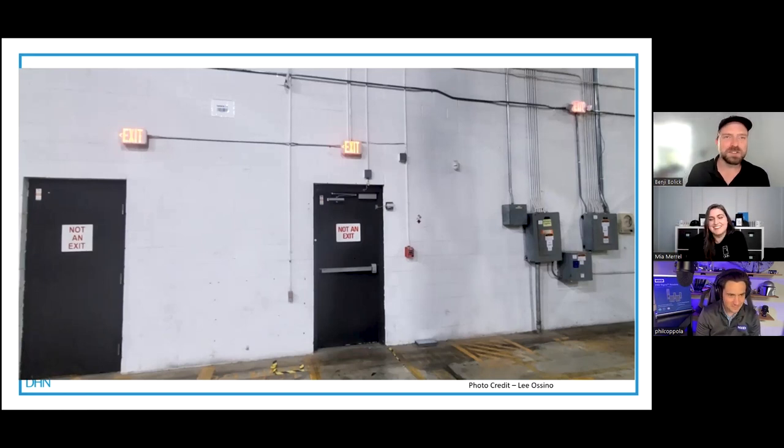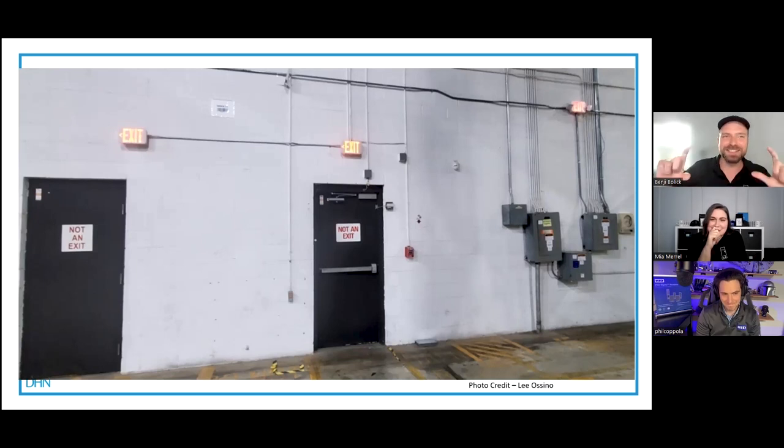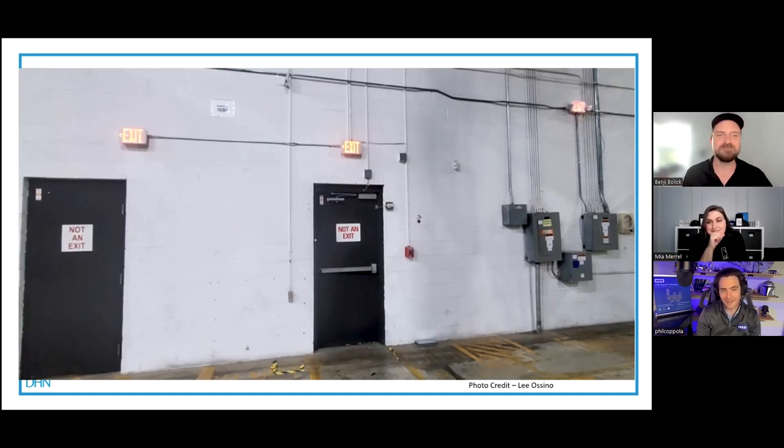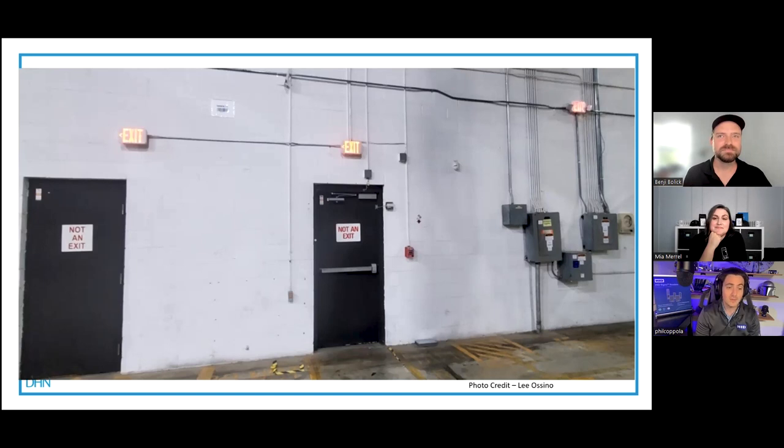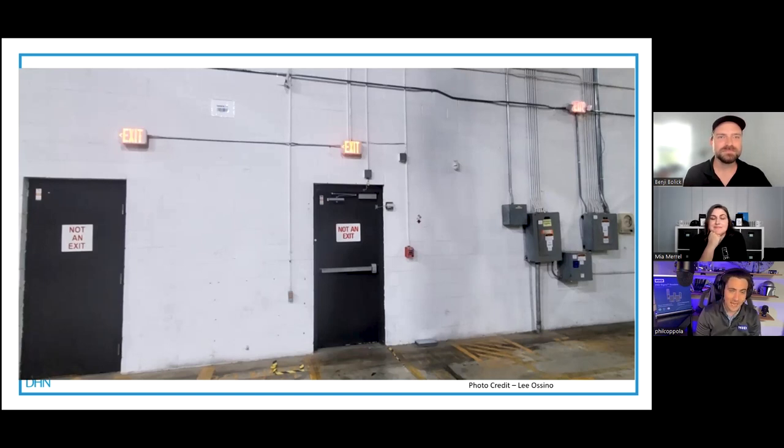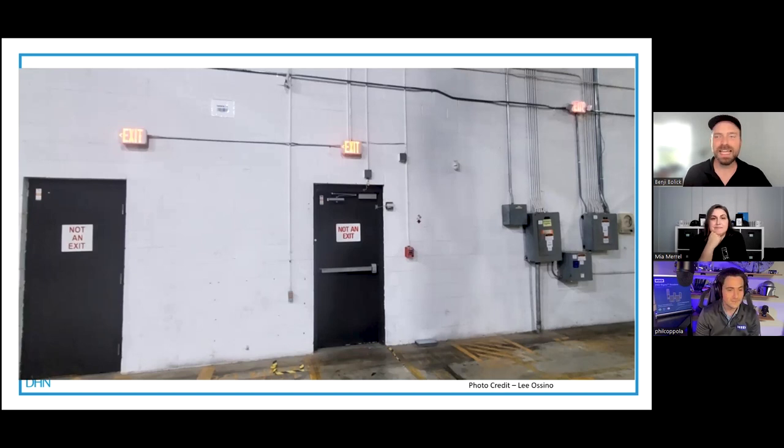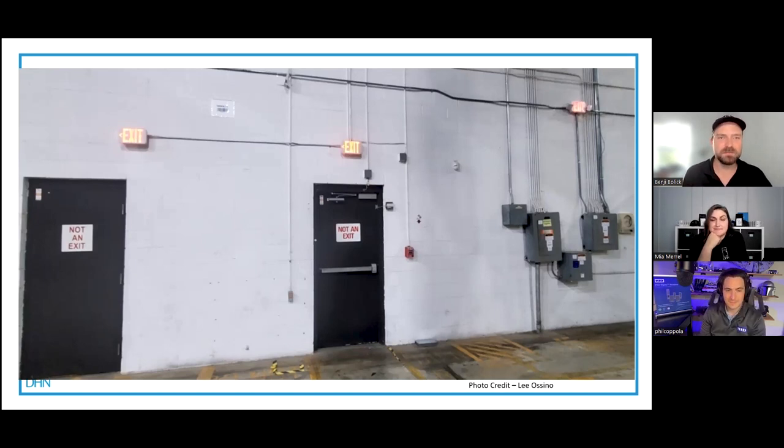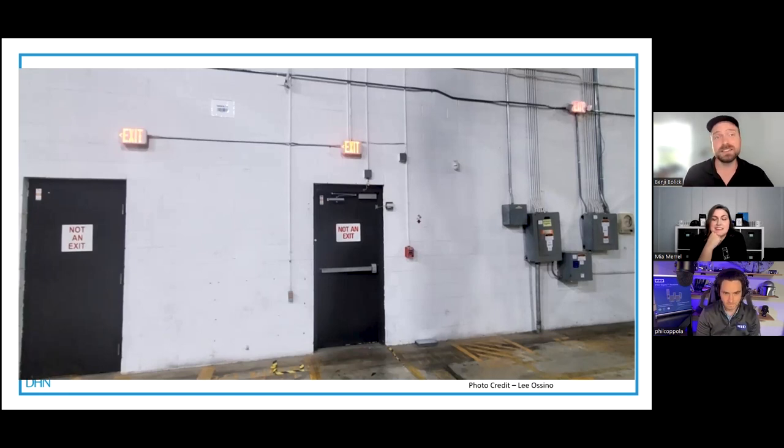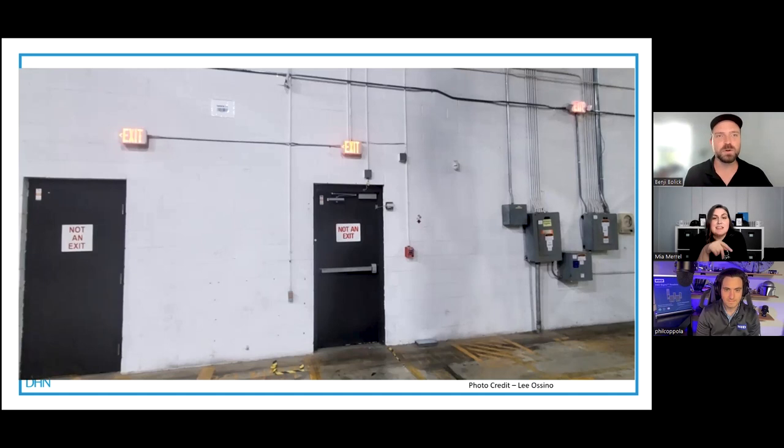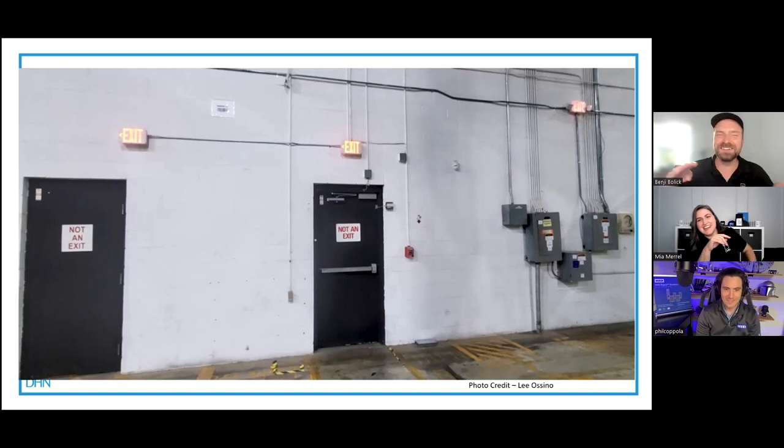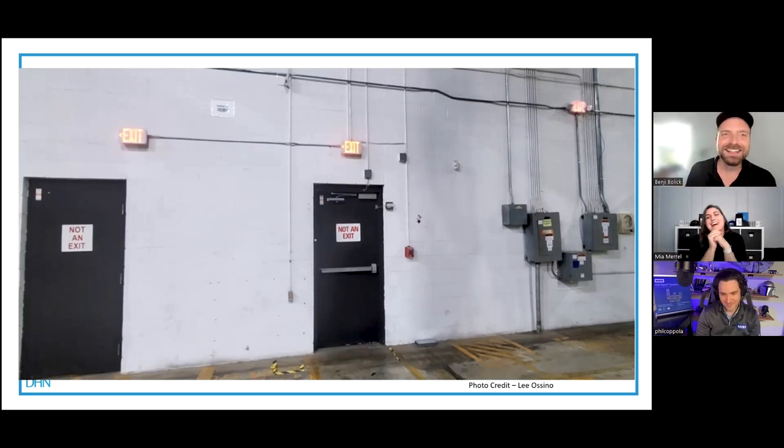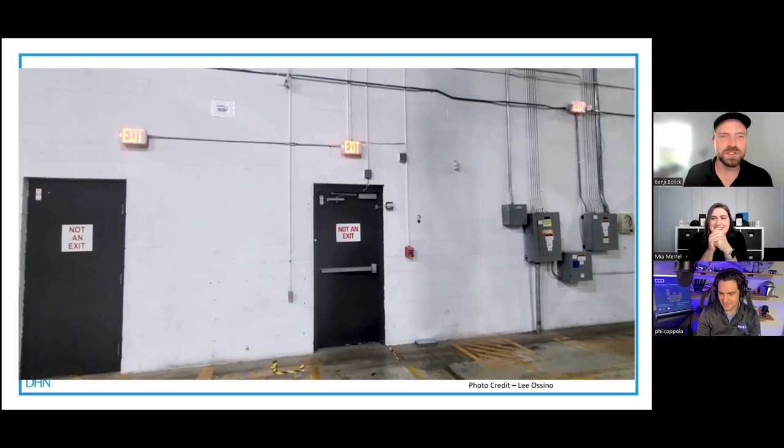On a scale of one to ten, this is a ten. In a life-threatening emergency, people will go to this door whether it's an exit or not because the exit sign is directly over it. Stopping their path of egress and having to figure something else out—anytime you have to think about the path of egress, that's a big problem. Door dork not approved.